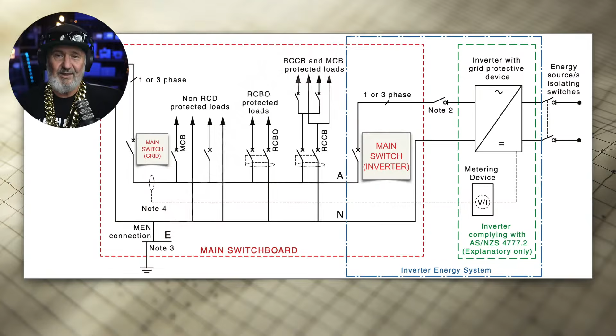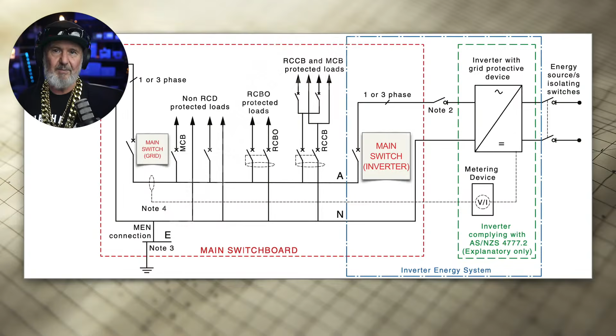3000's requirement is that main switches need to be identified from other circuits in some way. And there's lots of ways of identifying them. For instance, you can do it by distance. You can group them together and have a gap. It's pretty common in New South Wales, I've seen, to have a half-pole gap between main switches and other circuits that they control. You can do it by labelling. You can do it by colour. So you actually might have a main switch that's got a different coloured tongue, like a red isolator tongue. So this is just one way of identifying the difference between a main switch and the circuits that it provides. Cool.